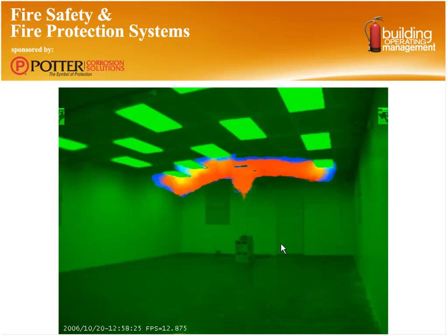In the case of smoke, what we're actually looking at is what we call aging, or aging analytics, of the actual smoke. How long has that smoke been seen by each pixel? And the different colors that you're seeing here are the associated timelines. If the analytics say, "Hey, I've seen that smoke for 8 seconds," it turns all of those pixels blue in its recording, and the orange means a little bit newer smoke, and so on down the line.